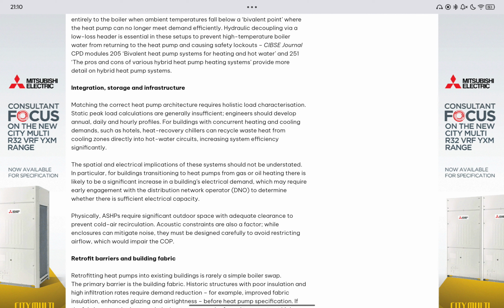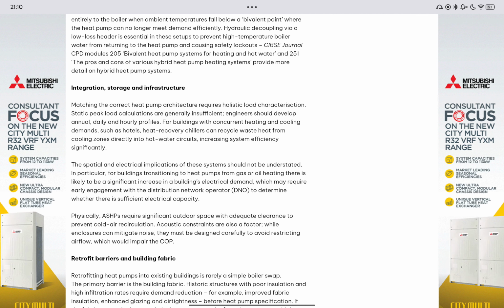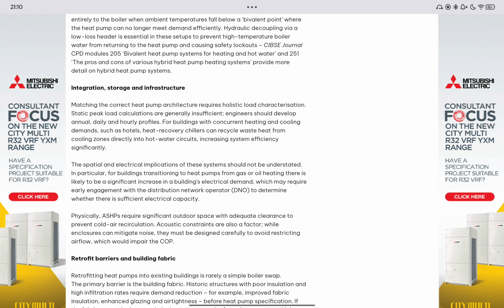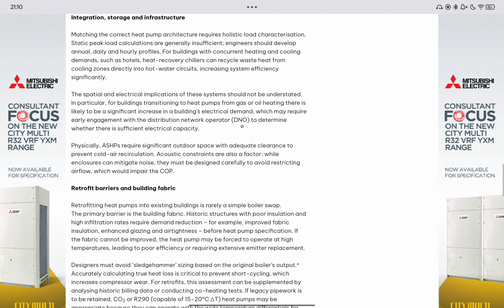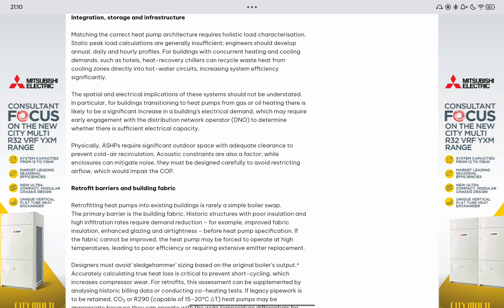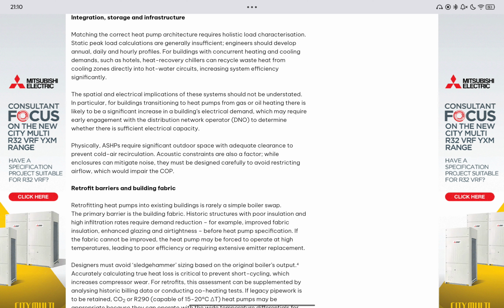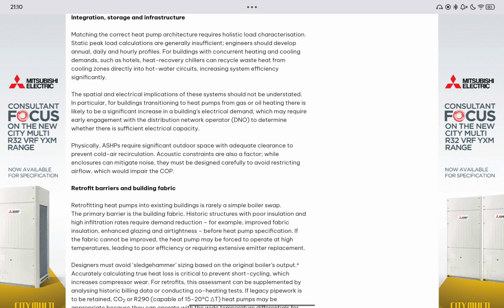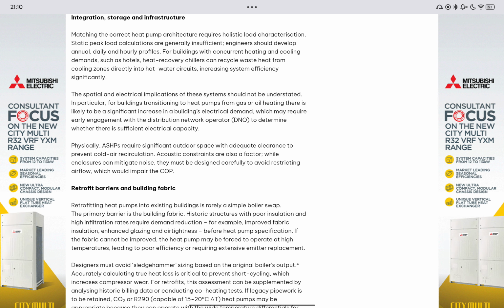For buildings with concurrent heating and cooling demands such as hotels, heat recovery chillers can recycle waste heat from cooling zones directly into hot water circuits, increasing system efficiency significantly. The spatial and electrical implications of these systems should not be understated. In particular, for buildings transitioning to heat pumps from gas or oil heating, there is likely to be a significant increase in a building's electrical demand, which may require early engagement with a distribution network operator, or DNO, to determine whether there is sufficient electrical capacity.